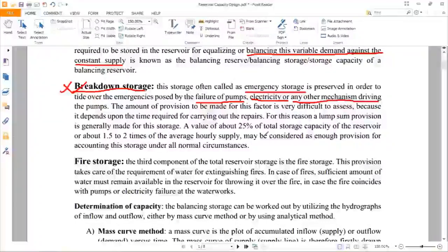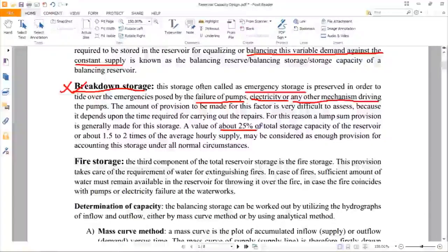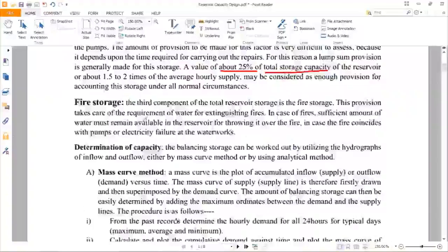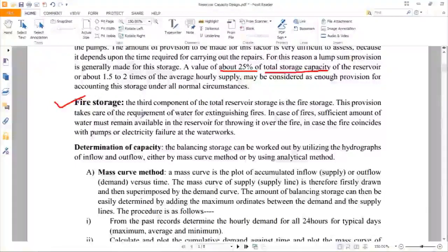Whenever you are calculating the balancing storage, you also have to maintain a separate breakdown storage, which will be supplied in case of any breakdown of electricity, machinery, or pumps. Generally, a provision is made that 25 percent of the total balancing storage is taken as the breakdown storage.